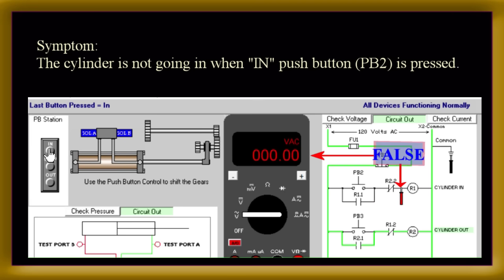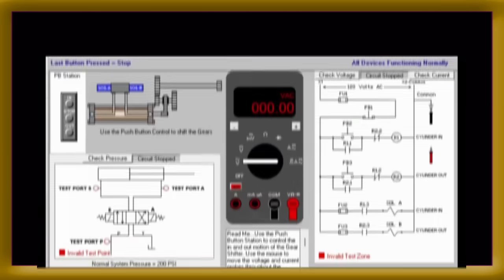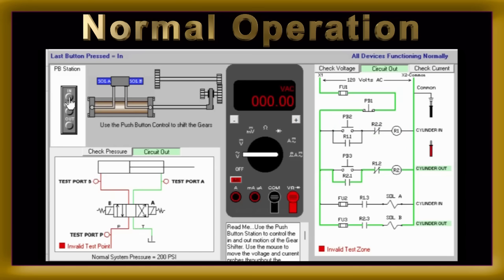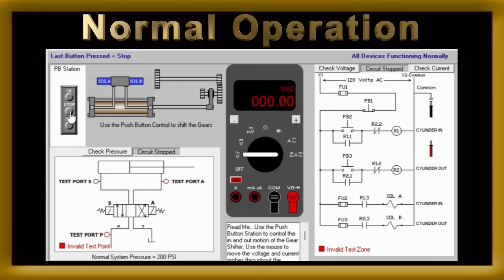The false, zero-volt reading after the normally closed contact for relay 2 shows us R2 is stopping R1 from turning on. In the previous example, the issue was just an operator error. As we discovered with this circuit, the operator must press the stop push button first to turn off the cylinder out relay, before pressing the in push button.